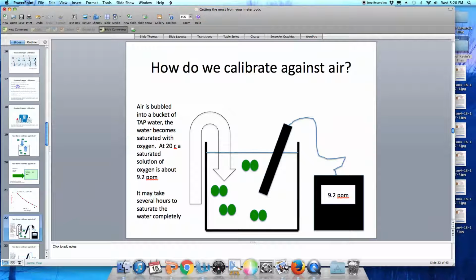Now, how do we calibrate against air or against oxygen-saturated water in the laboratory? This is a very good way to check your meter, and it is very reliable. So what you're going to do is you're going to have a bucket of tap water, not distilled water, but tap water. And into that bucket of tap water, you're going to bubble a stream of air, and that will cause the oxygen in the air to become dissolved in the water.